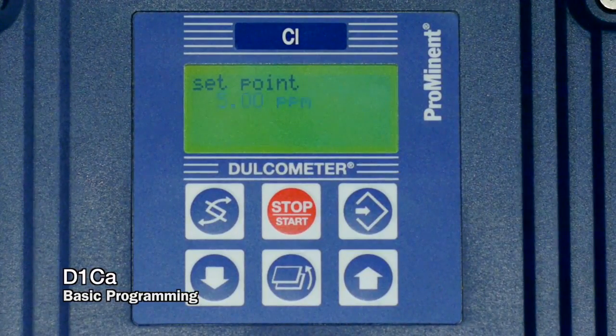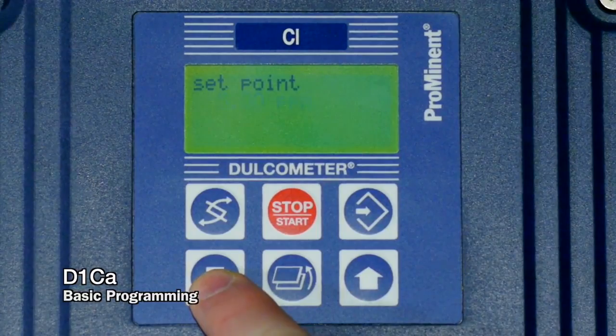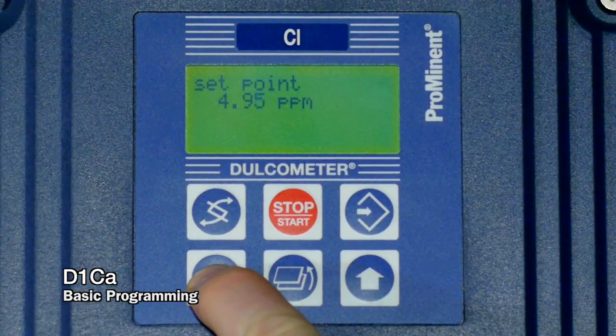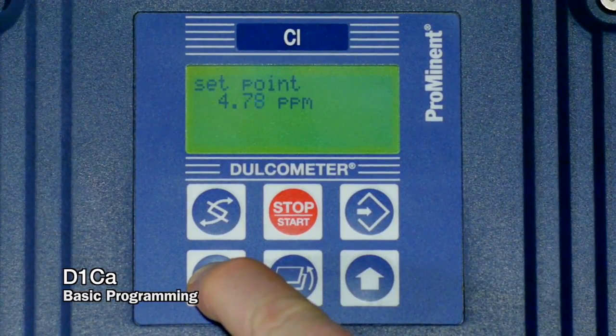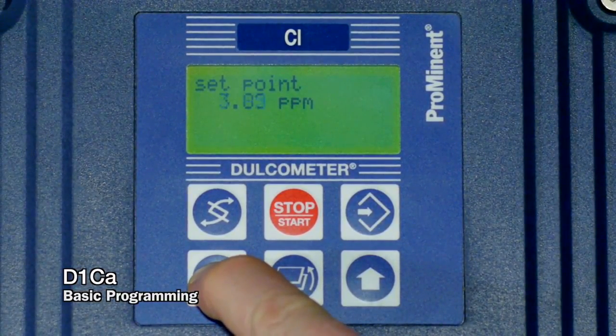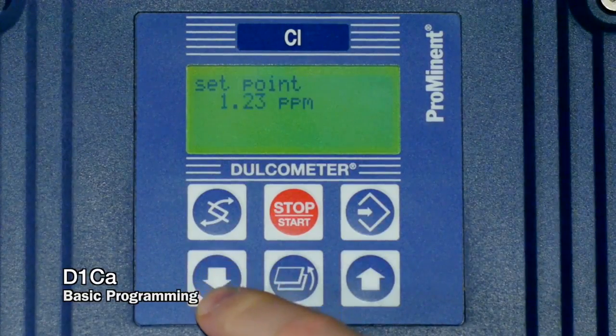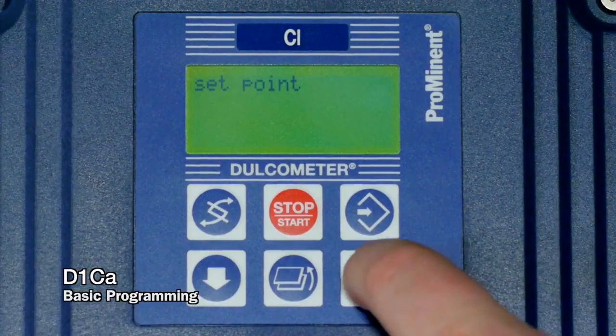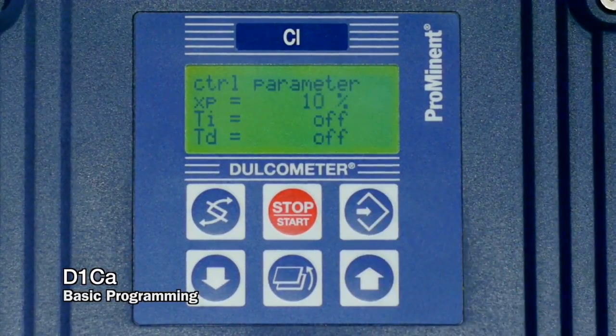Set point here for this D1C on chlorine. Again, since we changed the measuring range to 10 parts per million, the default is going to go to 5 parts per million, which is half the measuring range. So I can increase or decrease that with the up or down arrow button. Very common might be 1 part per million. We're just going to set it to say 1.2 ppm. You hit the enter button.